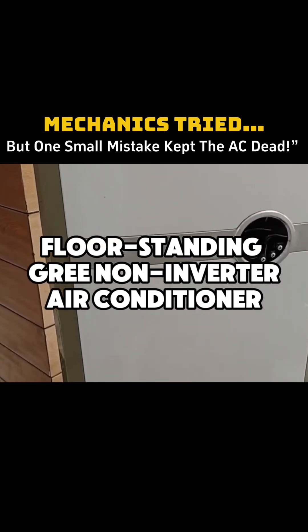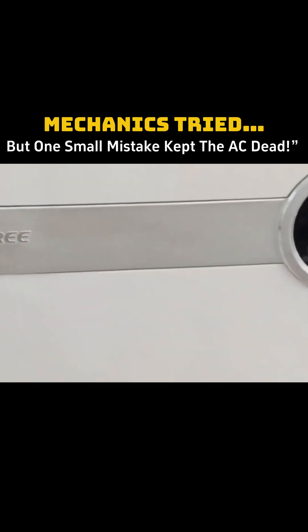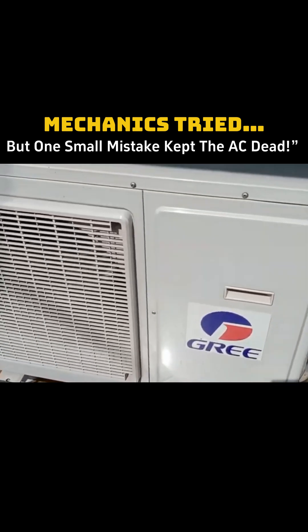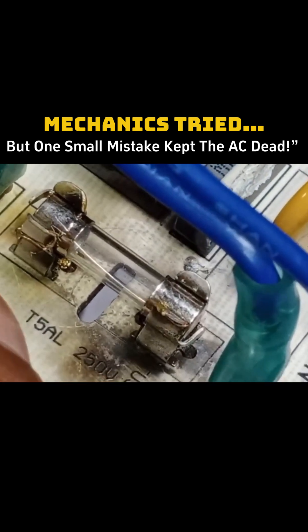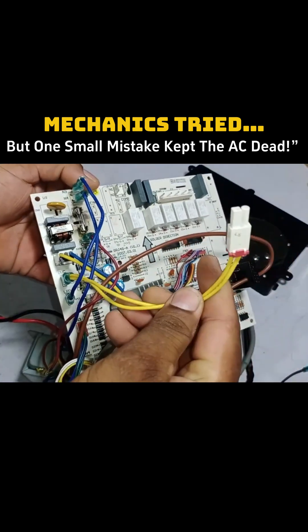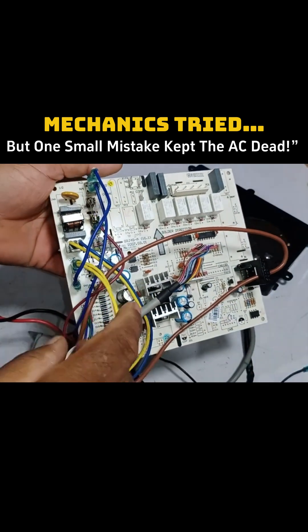There's a floor-standing GREE non-inverter air conditioner that several mechanics tried to repair, but they couldn't fix it because of the tools they were using. Even if they had the experience, they weren't using the tools properly, and the issue is that its fuse was burned out very badly. Someone replaced the fuse, but there is still a problem after replacing it. For the high pressure, there is a switch available, but the installer is not installing it, which is causing the problem.